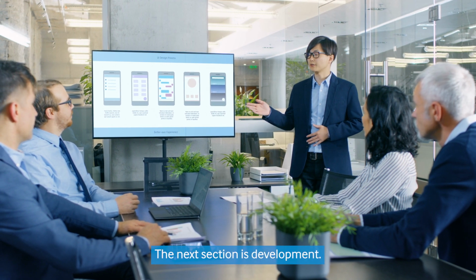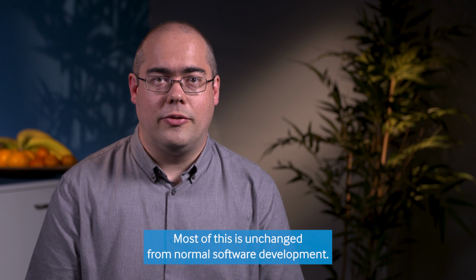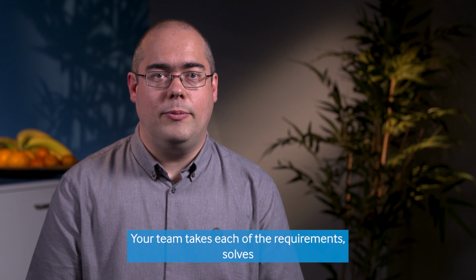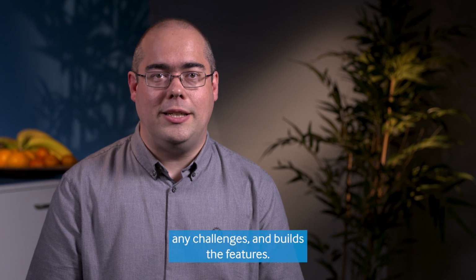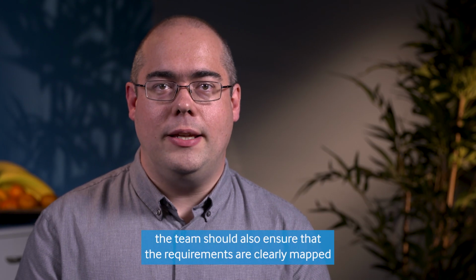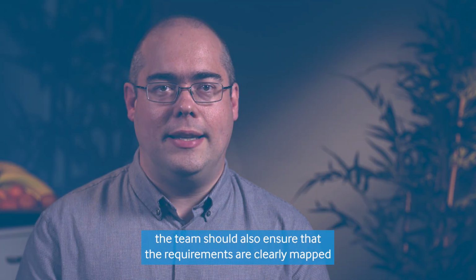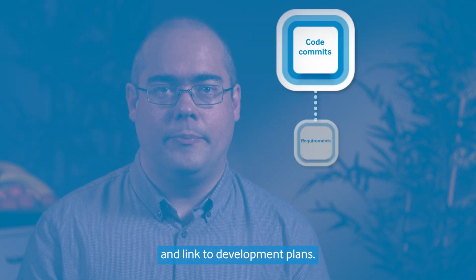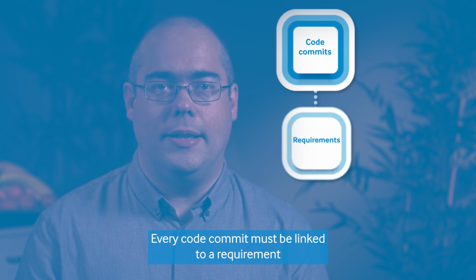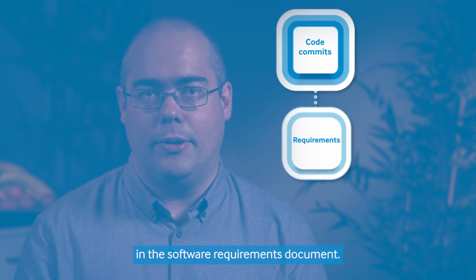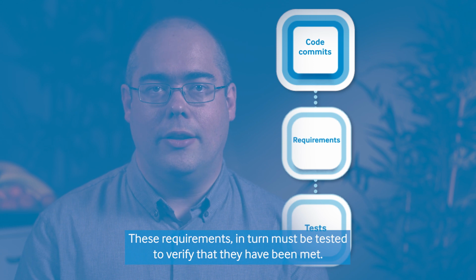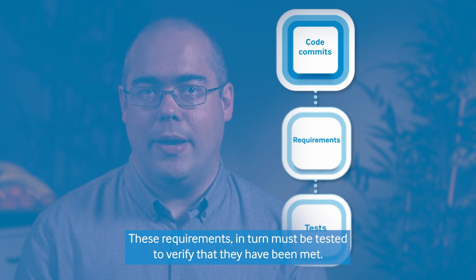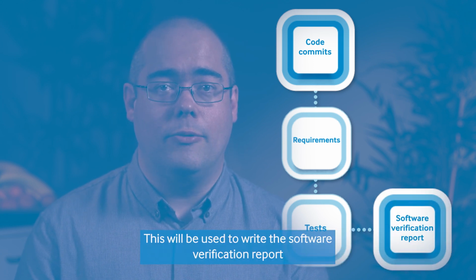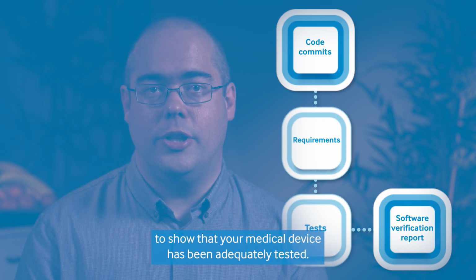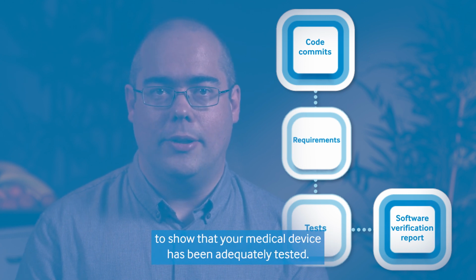The next section is development. Most of this is unchanged from normal software development. Your team takes each of the requirements, solves any challenges, and builds the features. With medical device development, the team should also ensure that the requirements are clearly mapped and linked to development plans. Every code commit must be linked to a requirement in the software requirements document. These requirements, in turn, must be tested to verify that they have been met. This will be used to write the software verification report to show that your medical device has been adequately tested.